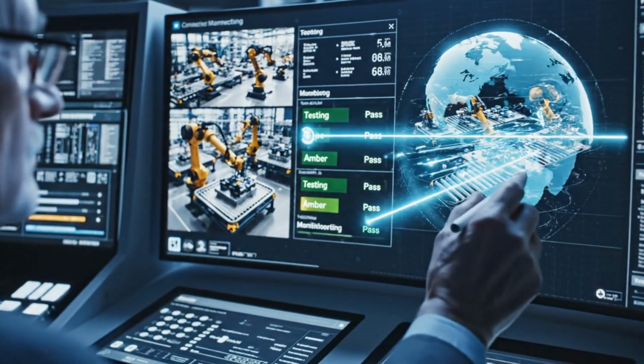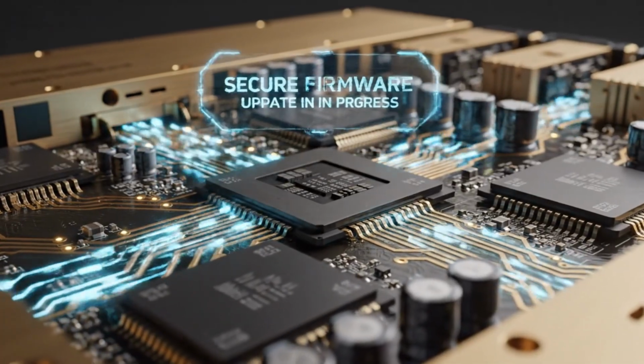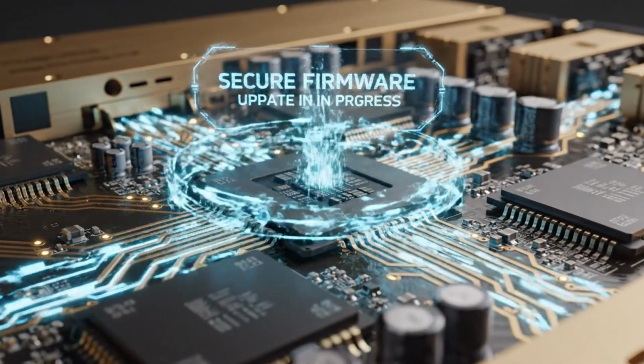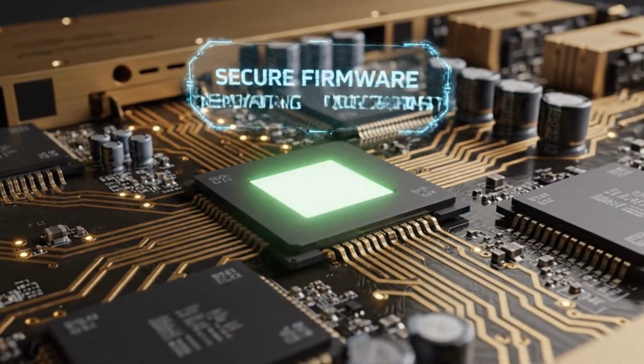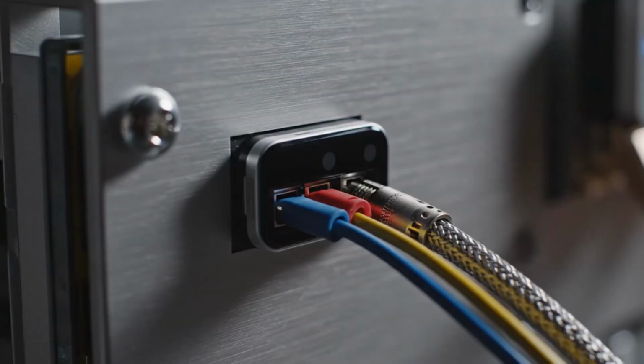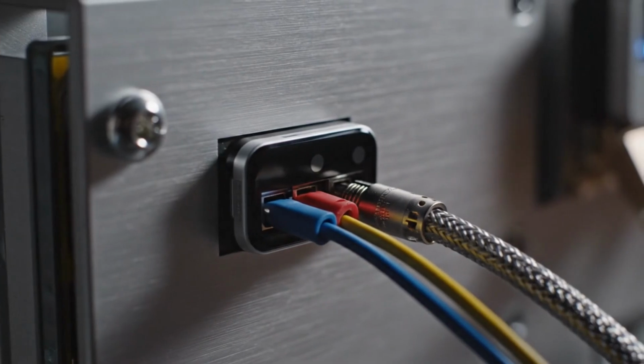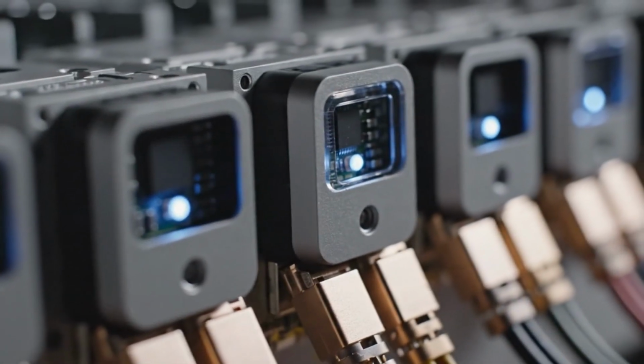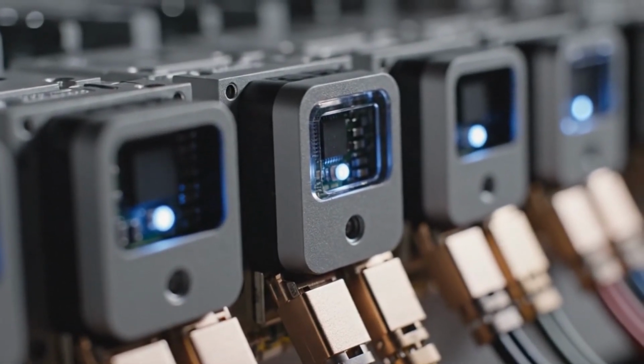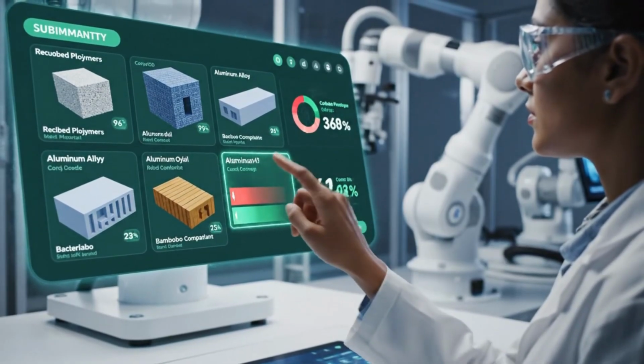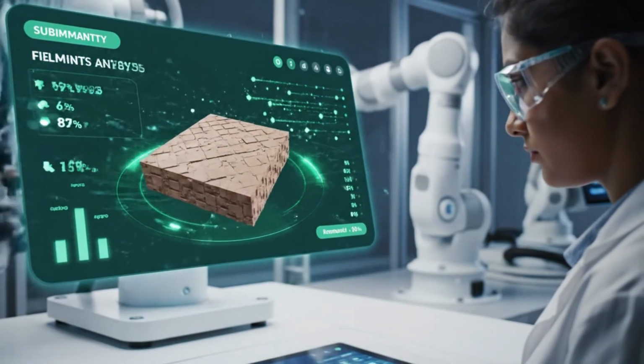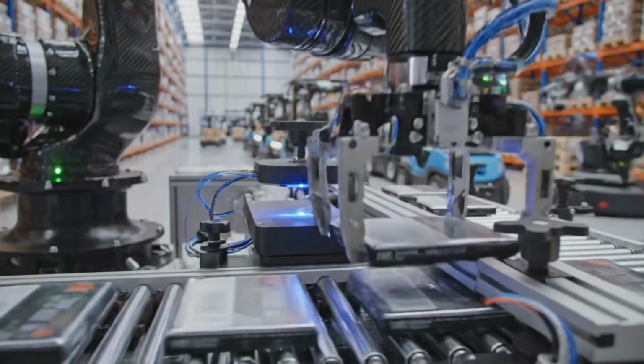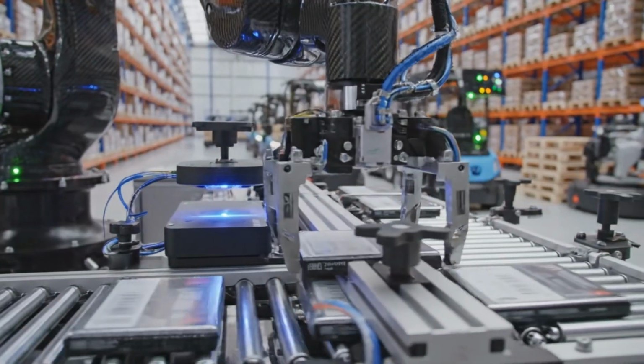Validation begins with functional verification. Each assembled unit, whether a circuit breaker, protection relay, power distribution panel, or intelligent controller, is connected to automated test benches that verify electrical continuity, signal accuracy, and control behavior. Inputs are injected with precision. Outputs are measured and compared against strict reference models. Deviations are logged instantly and traced back to specific assembly parameters.